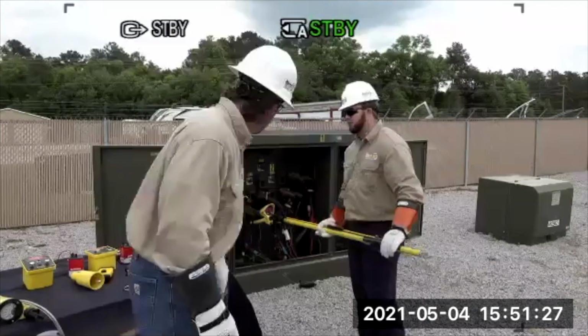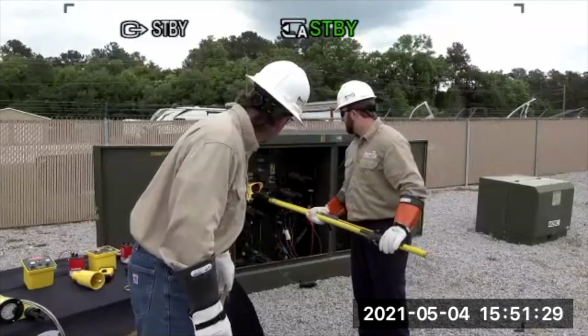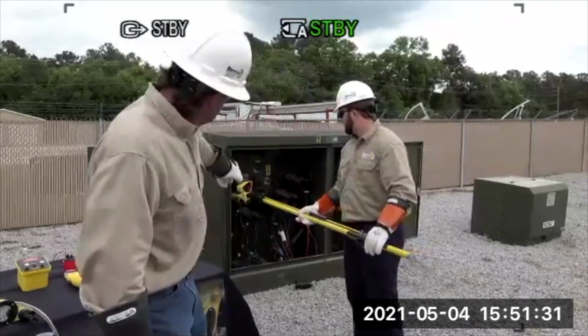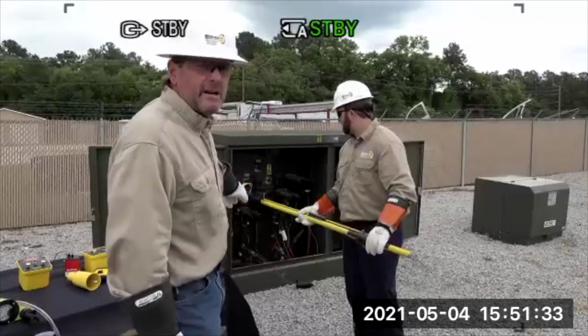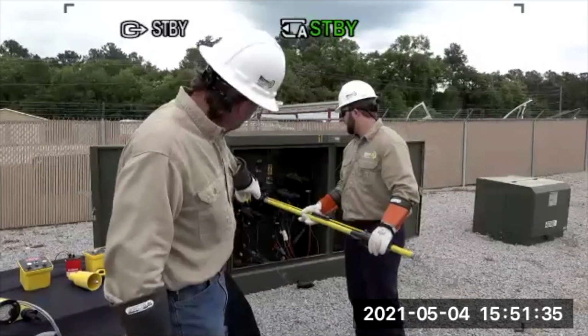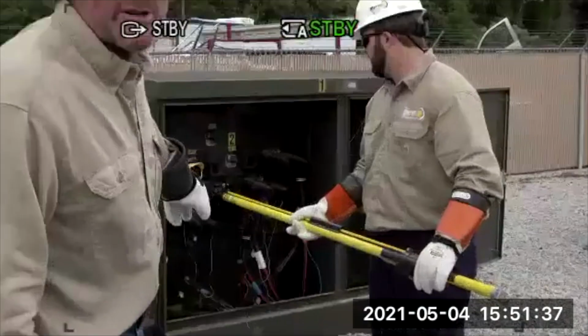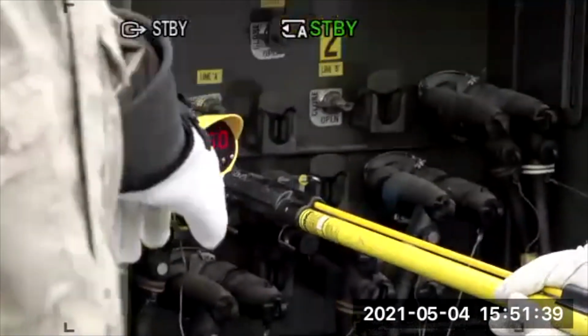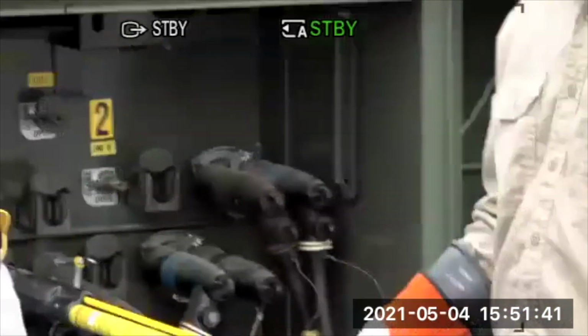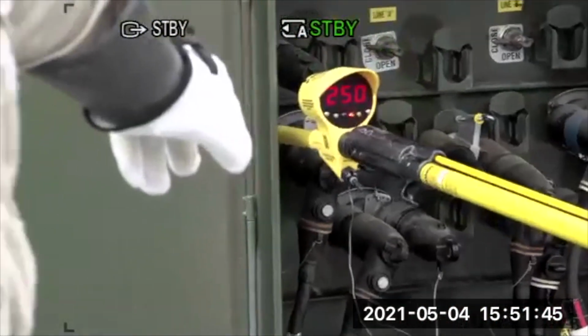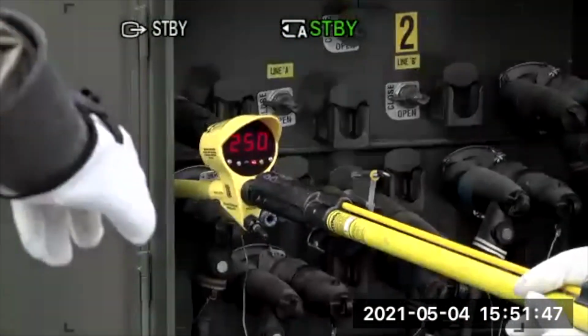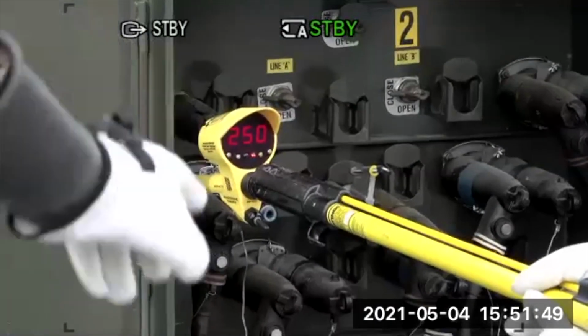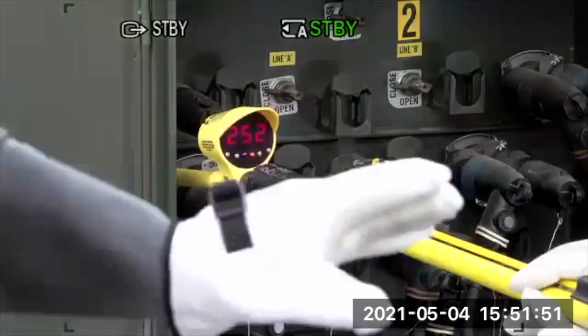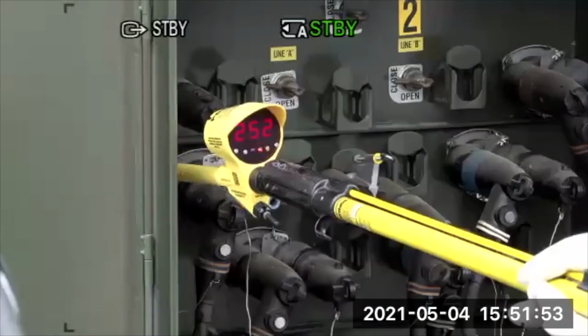Want to go to the last one, Parker? There you go, so we see our red phase there. So the sequence is blue as our reference, white, and our last in phase is going to be our red, which is close to 240 degrees out, and then you see a red light. So it's just super safe, real-time information.